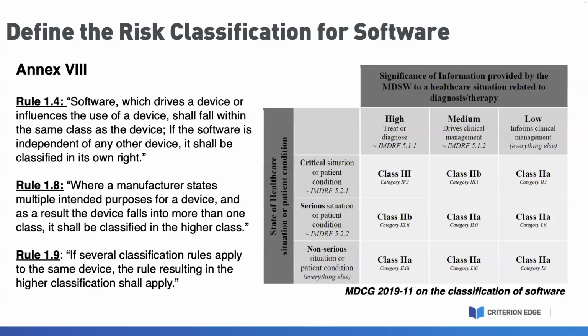That's going to be software that can provide information for serious or non-serious health conditions. But if you fall under serious health conditions, you could be classified as category 1 if it's providing information to inform but not drive clinical management. Otherwise, it's really hard to fall under this category 1. They've really made it a very narrow definition.